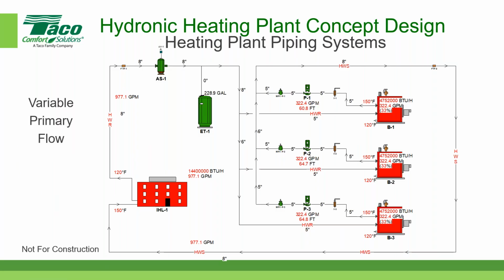But in general, you'll notice that the air and dirt separator is also on the suction side of the pump and the boiler. So the air separator is at the lowest pressure in the system. Hopefully that helps people with that.